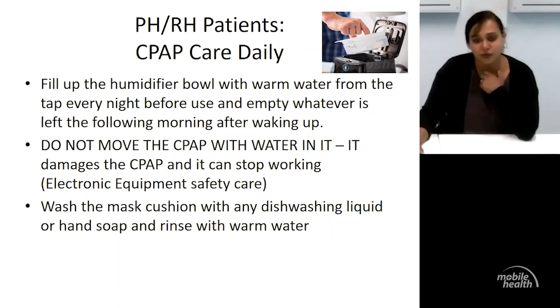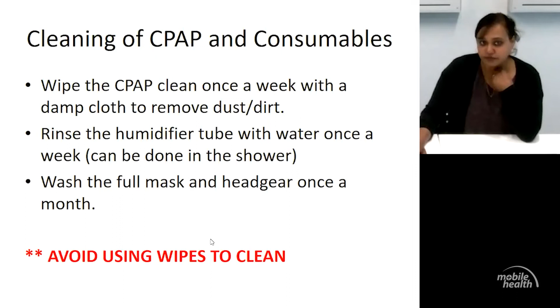We don't recommend using wipes to clean your mask or your machine, a humidifier bowl, etc., because the alcohol in some of those cleaning wipes can sometimes damage the silicone in the mask. So it's better to use soap and water. The hose, you can rinse it once every week or even a fortnight. If patients are in their own home or private hospitals, they can just take it into the shower and give it a rinse and then hang it up during the daytime to dry out. They shouldn't be put outside in the sun, otherwise they will crack. The rest of the mask, like the frames and the headgear that they have on their head, can be washed once a month.